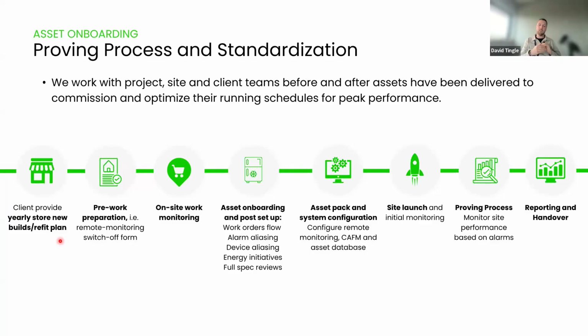I'll go into detail on the actual control solution later. So all that work's carried out on site, and we've turned off the remote monitoring. That step-by-step process of onboarding those assets - at the point they're connected, they hit our system. This is the onboarding stage in terms of commissioning, and that works across multiple sections: device aliasing, alarm aliasing, the work order flows, energy initiatives, and a full spec review.